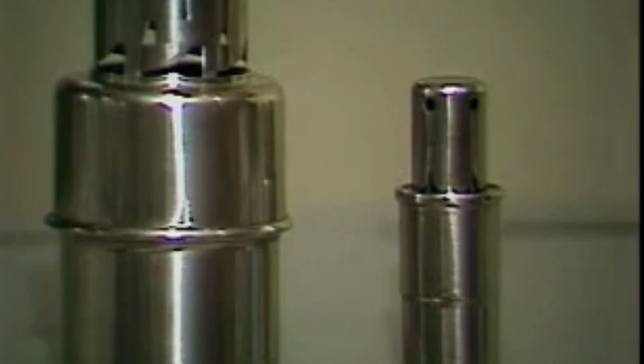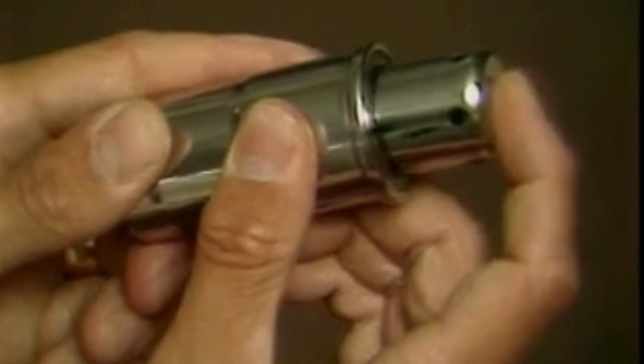required for the control. The control mechanism of the valve consists of a self-contained open chamber cartridge assembly with unobstructed flow passage that eliminates accumulation of particles and debris. All internal working parts are stainless steel when working in freshwater or Monel for application in seawater. The cartridge assembly consists of a spring-loaded cup. The cup is guided at 2 points and utilizes the full available differential pressure across the valve to activate the cup and thereby reduce friction and eliminate binding. It has a thin orifice plate for self-cleaning of the variable inlet ports over the full control range.